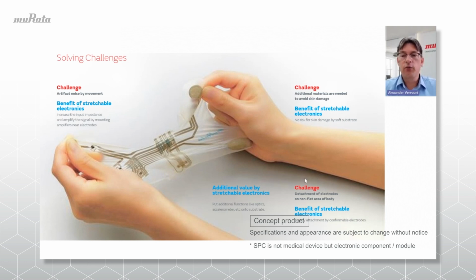In addition, traditional materials can also be a limitation to wear time. And stretchable printed circuits can make sure that electrodes can conform better to the skin and reduce the risk of detachment. And the benefit of this is enabling longer wear time and also better attachment on, for example, measurement electrodes to the skin. And this is especially the case on surfaces which are uneven and can sort of bend or twist during the usage of the device, such as joints or bony areas.